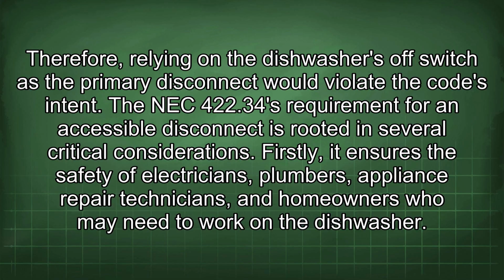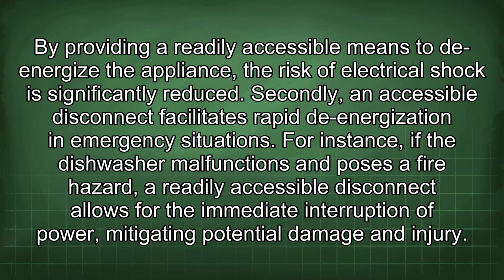The NEC 422.34's requirement for an accessible disconnect is rooted in several critical considerations. Firstly, it ensures the safety of electricians, plumbers, appliance repair technicians, and homeowners who may need to work on the dishwasher. By providing a readily accessible means to de-energize the appliance, the risk of electrical shock is significantly reduced. Secondly, an accessible disconnect facilitates rapid de-energization in emergency situations. For instance, if the dishwasher malfunctions and poses a fire hazard, a readily accessible disconnect allows for the immediate interruption of power, mitigating potential damage and injury.